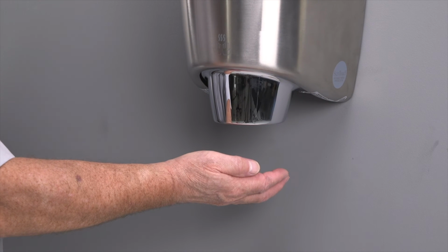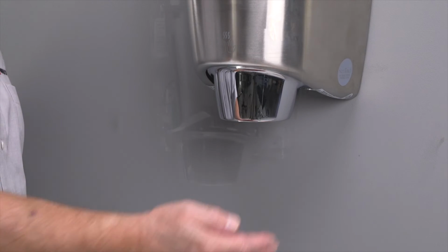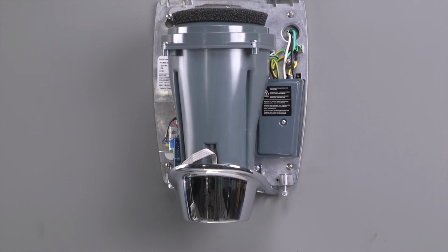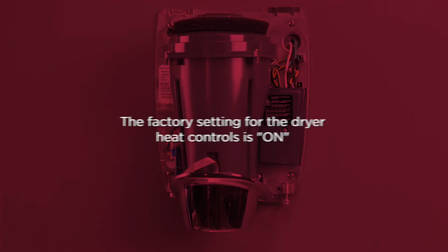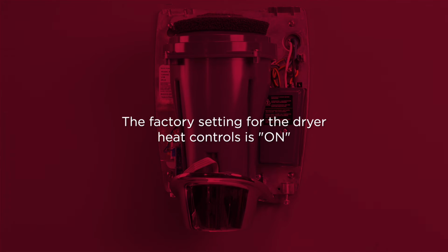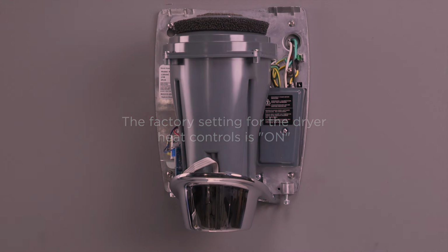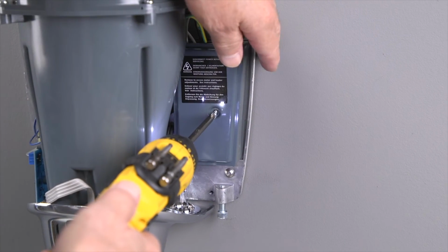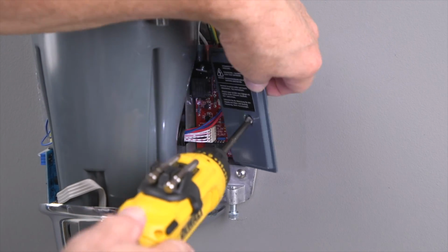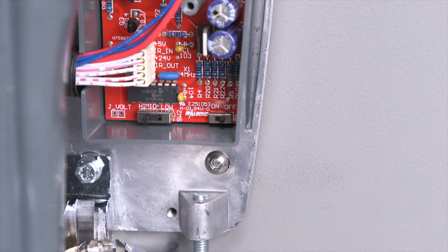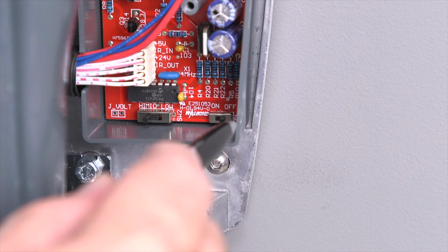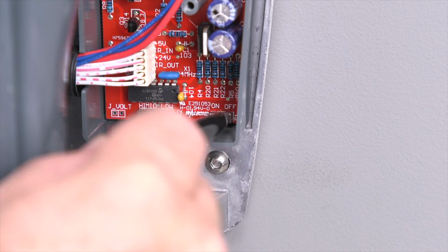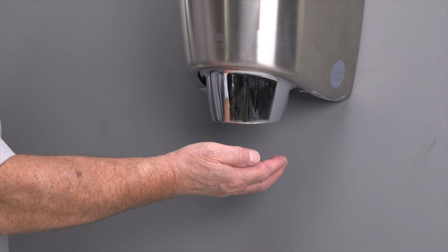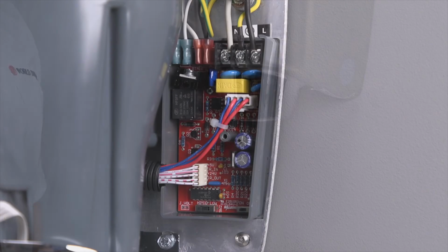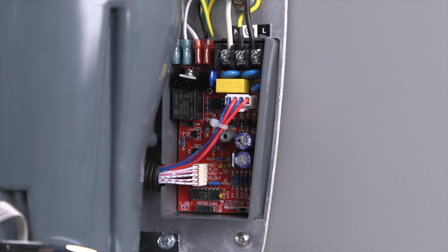If you've diagnosed that the dryer's air temperature is too cool, confirm the dryer's heating switch is on and properly functioning. The factory setting for the dryer heat controls is on. Remove the wiring compartment cover to access the heat switch. The dryer's heat switch can be positioned on or off. Try changing the heat switch position and notice if the dryer air temperature changes. If the dryer air temperature does not change, replace the main PCB.